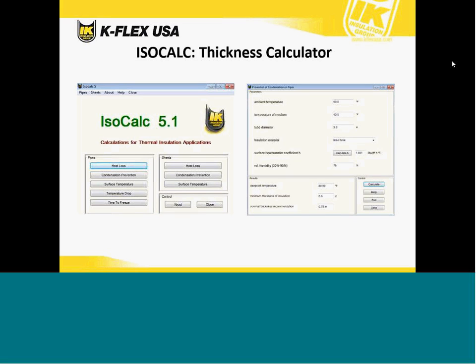Another benefit that K-Flex offers is our ISOCalc program. This is for engineers or users who need to take a look at what insulation would properly fit their application. It's a very quick and easy to use program where you just input several parameters such as ambient temperature, medium temperature, and the diameter, and it will calculate the thickness of insulation required to prevent a certain level of heat loss, prevent condensation, or give you a specific surface temperature. It's an easy to use program that's available for free download on our website.